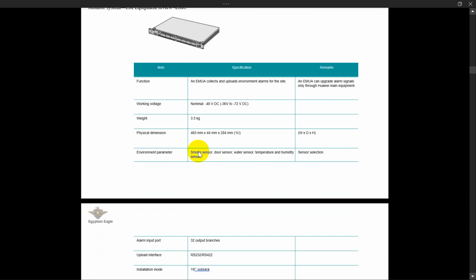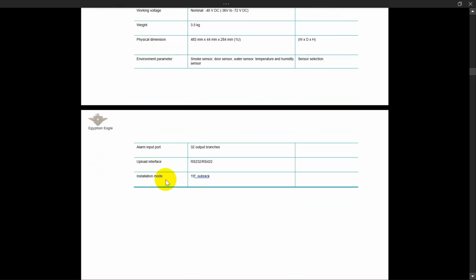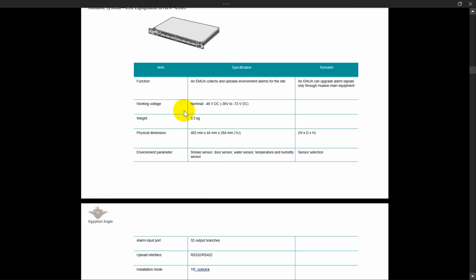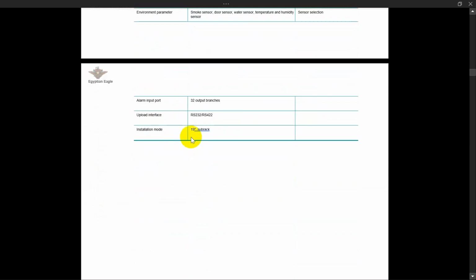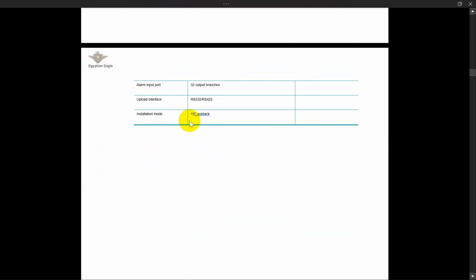We can configure all environmental alarms: sensors for smoke, door, water, temperature, over voltage, rectifier AC, rectifier DC, rectifier minor. All power alarms can be done through this unit or through the rectifier; both work. For this type of EMU, we can configure 32 alarms. For installation, it can be installed in a 19-inch rack. That's why I'm telling you we can use a chassis to fix the EMU and the rectifier.